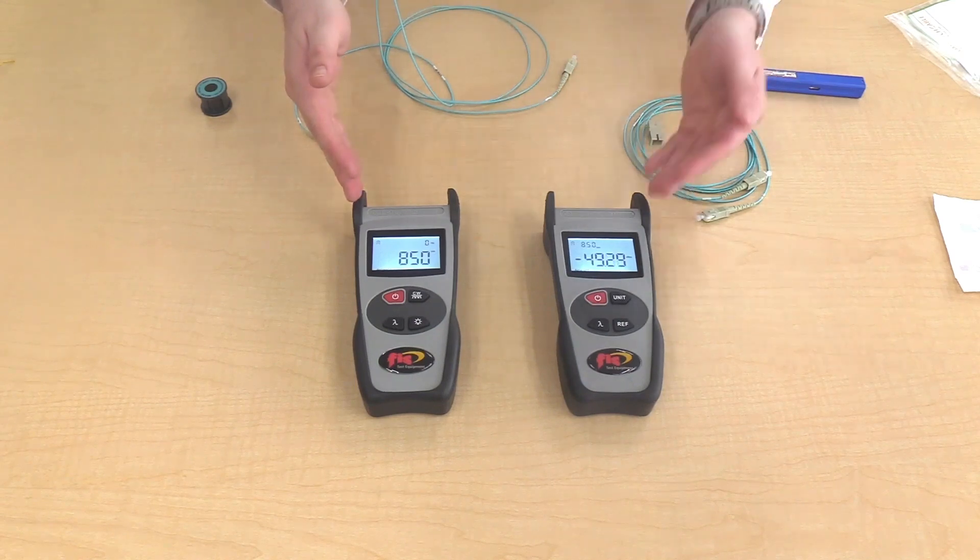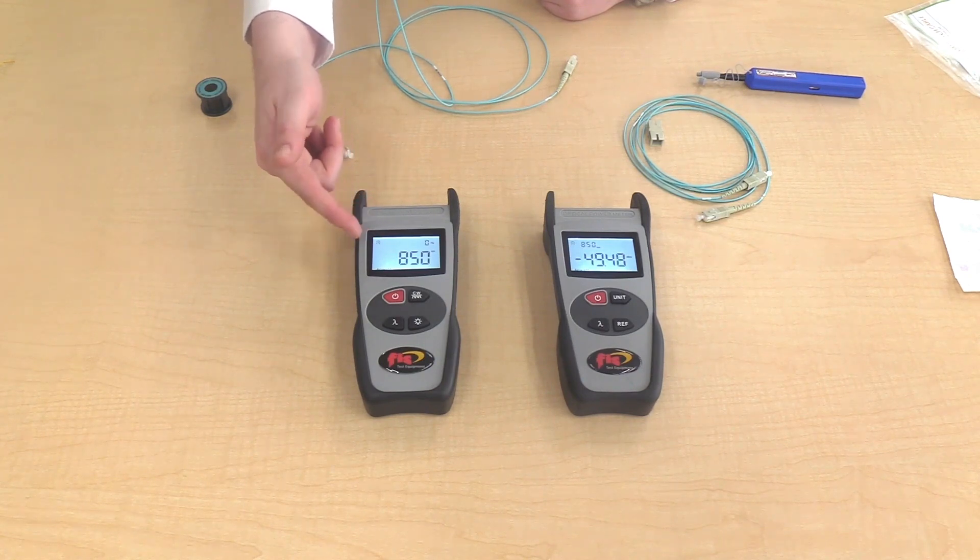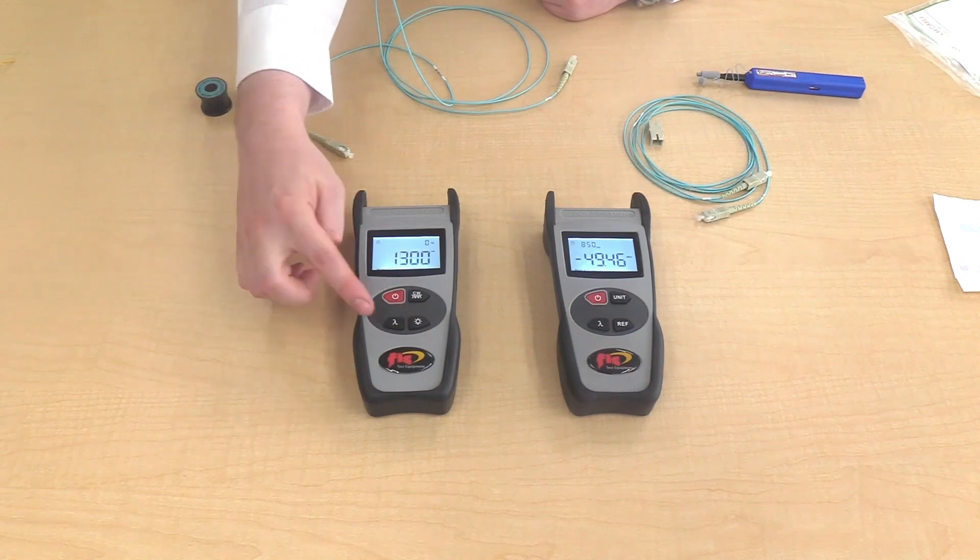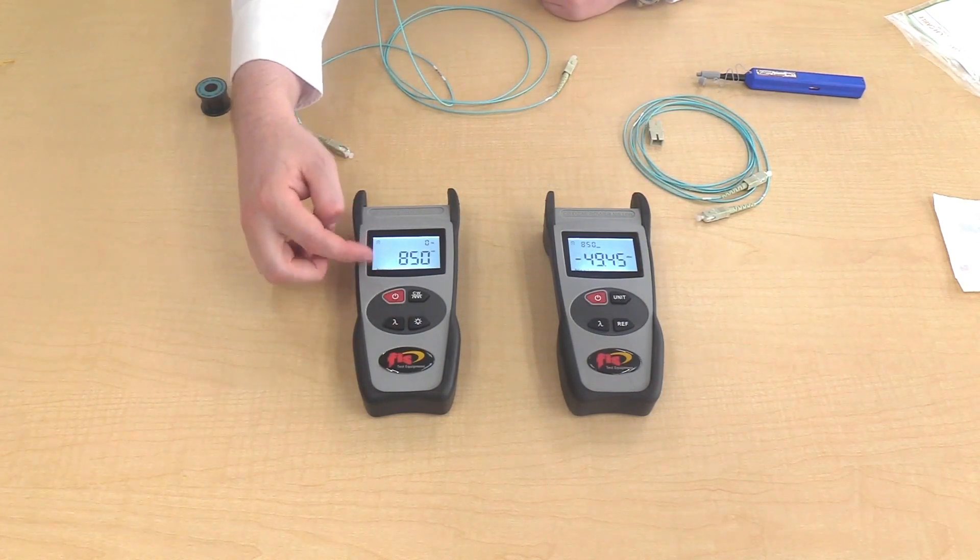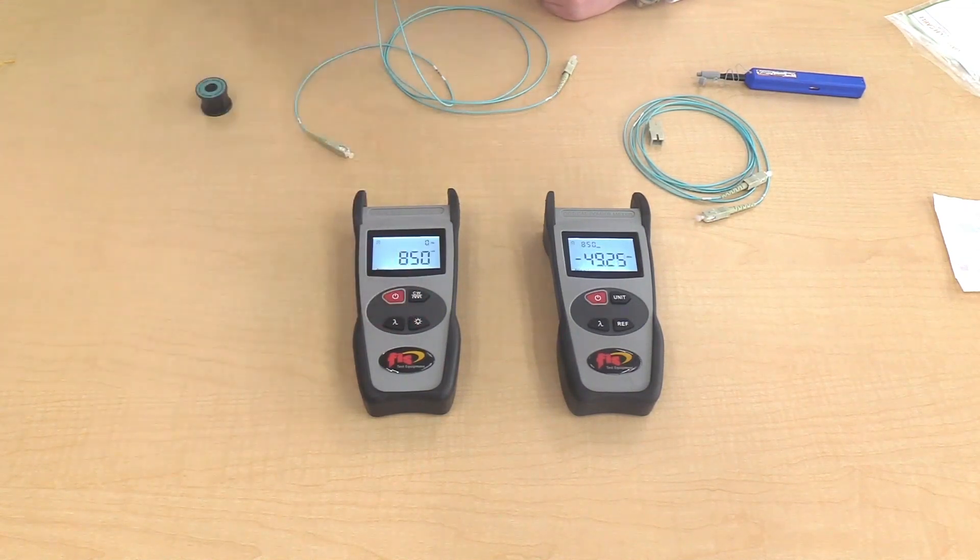You have the light source and power meter. For the light source, give it a few minutes for the laser to warm up. The display shows the current wavelength that is on. To change the wavelength, press the lambda symbol to 850 or 1300 nanometers. The top right button modulates the tone, and bottom right button is for the backlight.